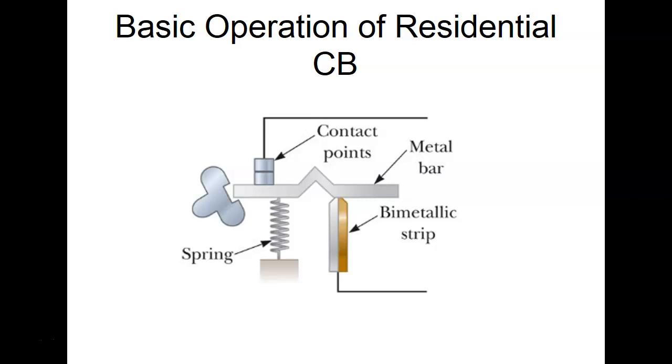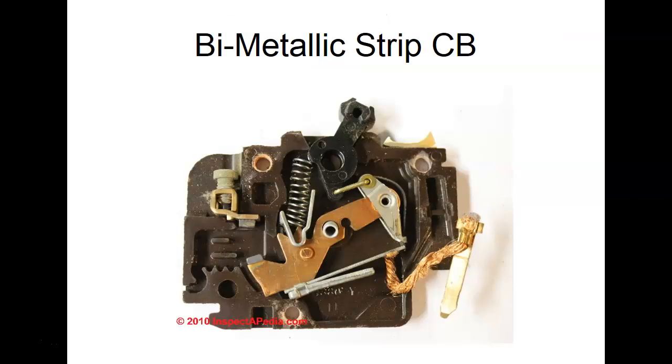And then that's why when you go in there and you try to reset it, if you don't give it time to do what? If you're in there when it pops, most of the time you can't do what? It won't reset. You have to wait for the strip to cool down. Yeah. This is actually inside of a typical circuit breaker. Spring loaded, when this thing trips, this thing bends, it causes this thing to pop out, causes this thing to pop down, right? Spring pushes.